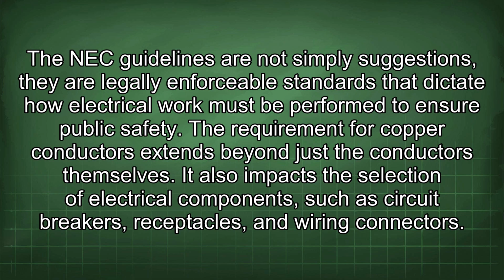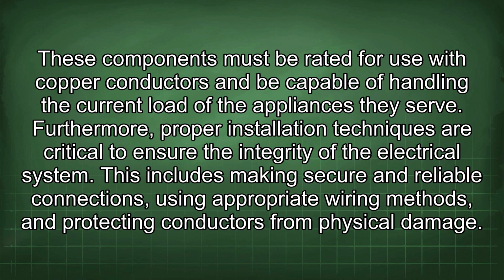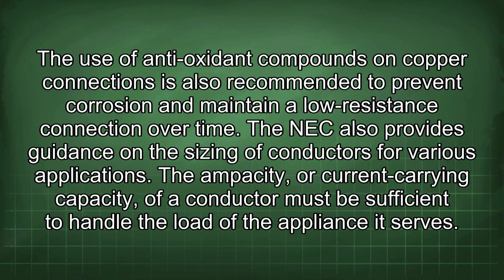The requirement for copper conductors extends beyond just the conductors themselves. It also impacts the selection of electrical components such as circuit breakers, receptacles, and wiring connectors. These components must be rated for use with copper conductors and be capable of handling the current load of the appliances they serve. Furthermore, proper installation techniques are critical to ensure the integrity of the electrical system. This includes making secure and reliable connections, using appropriate wiring methods, and protecting conductors from physical damage. The use of antioxidant compounds on copper connections is also recommended to prevent corrosion and maintain a low resistance connection over time.